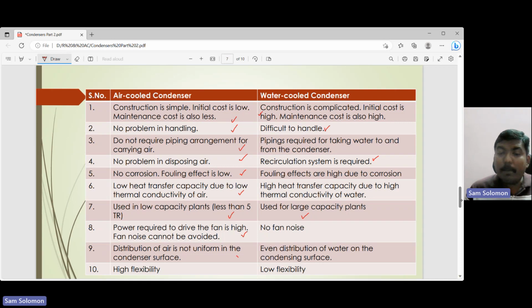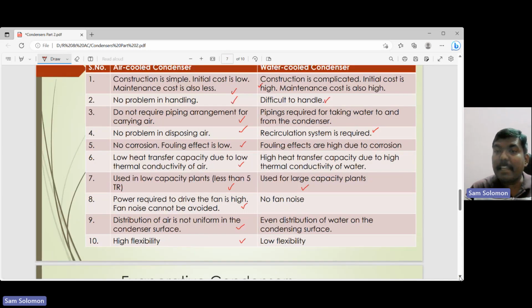Distribution of air is not uniform on the condenser surface. The flow of air depends on the speed with which the fan blows it, so there is a possibility that some air may bypass the coils. Whereas here you have even distribution of water on the condensing surface, because the water is going to flow through the tubes. And then you have high flexibility in case of the air-cooled condenser, whereas that sort of flexibility cannot be expected in case of the water-cooled condenser. So the difference has been very well represented by Khurmi in his textbook. So this is what water-cooled condensers are all about.